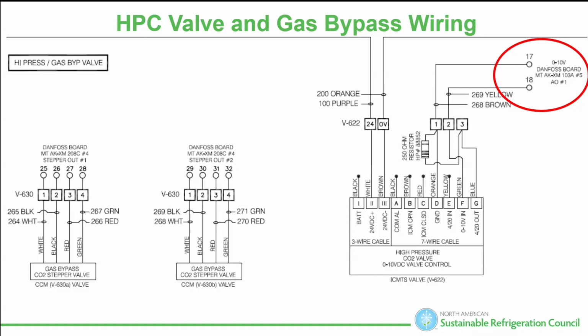I also need to make sure the temperature probe coming out of the gas cooler is about 6 inches out. I want to put it at about 4 o'clock, 7 o'clock on the pipe, but don't just insulate it with duct tape. Thermal paste is awesome, but then wrap it with Rubatex, and then get yourself a little piece of vinyl PVC wrap. What if you're in Miami? That Rubatex will break down in 6 months, and now I'm not protected. That temperature sensor is very important in driving this high pressure control valve. So we're talking about electrical, but we've got to talk about our inputs as well. So make sure you've got a good input.